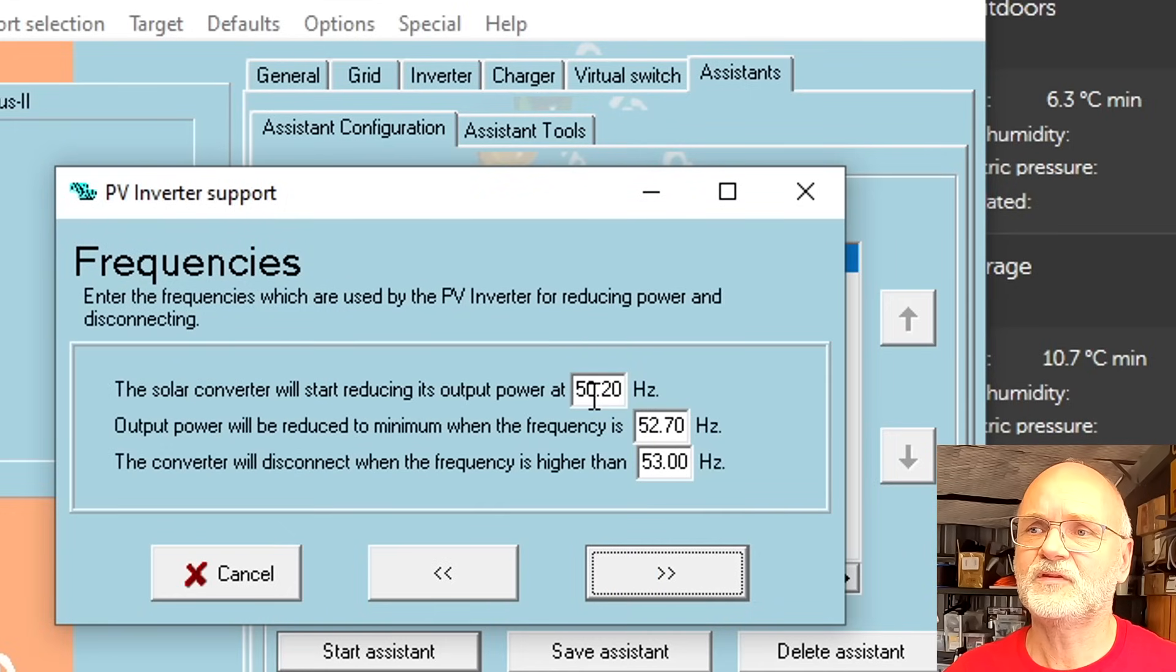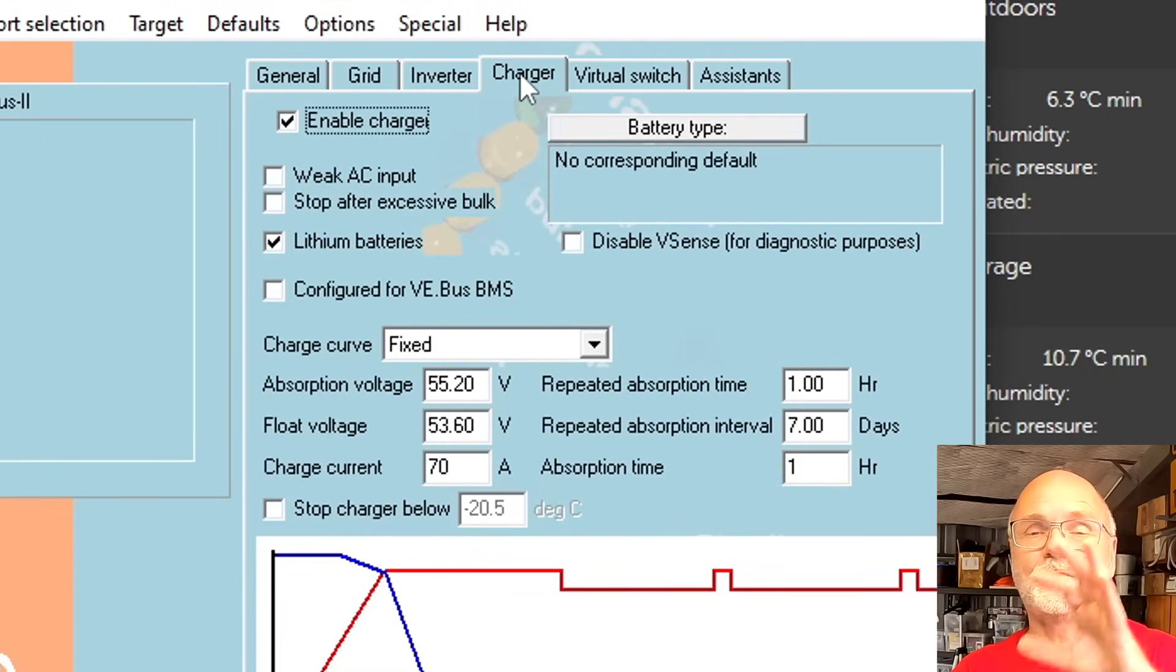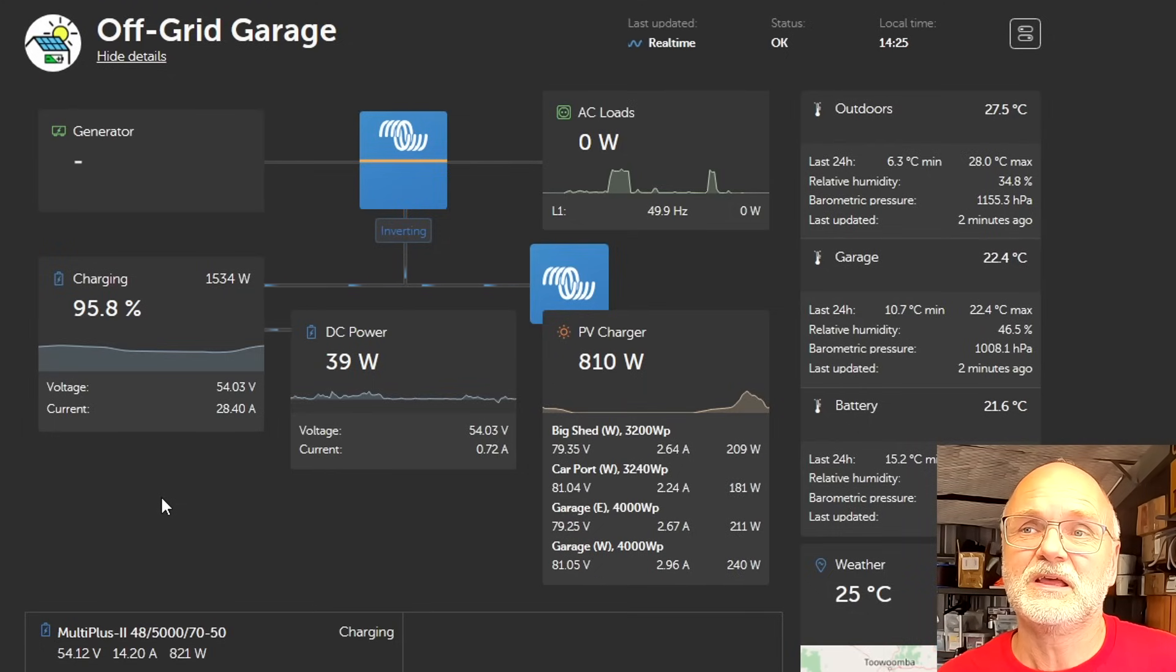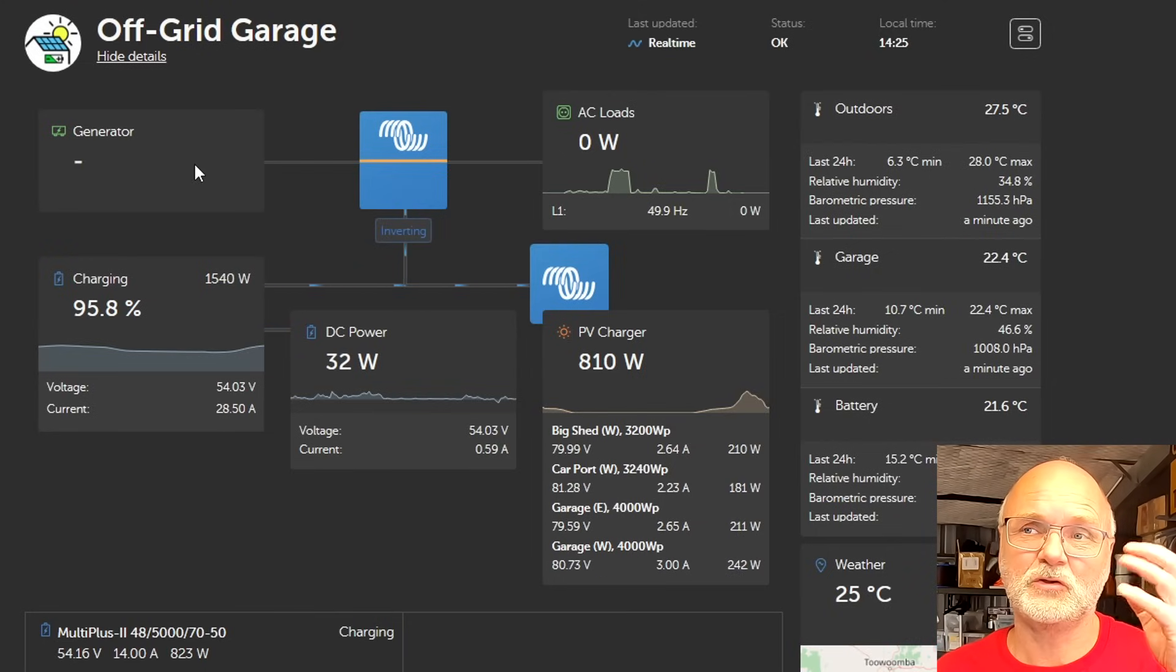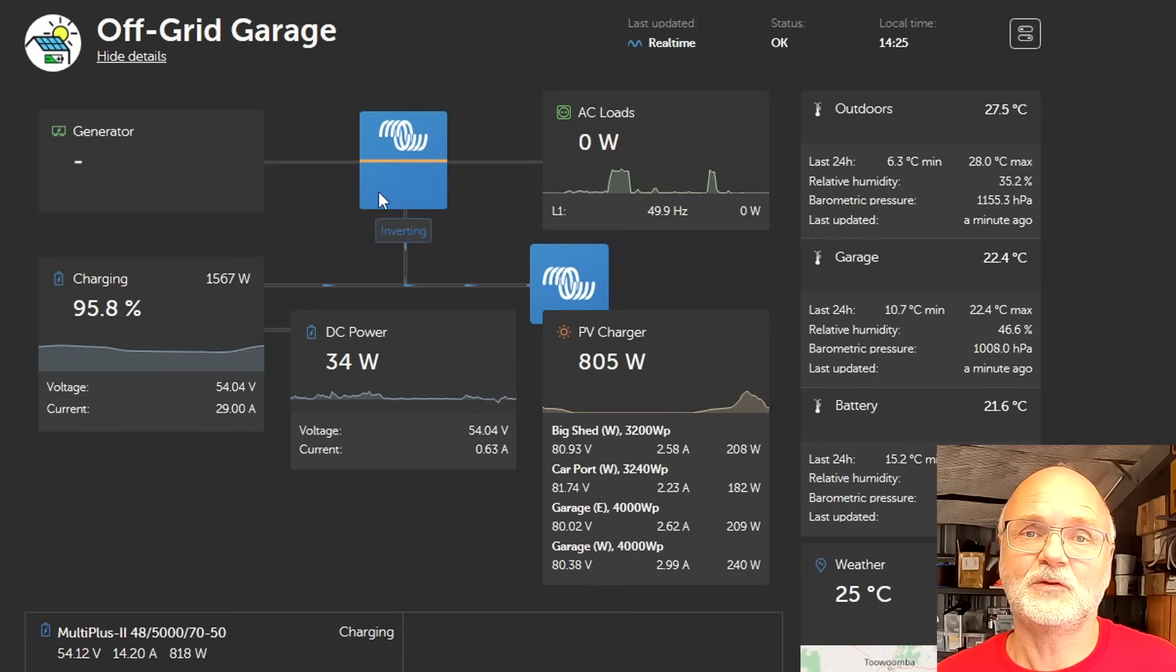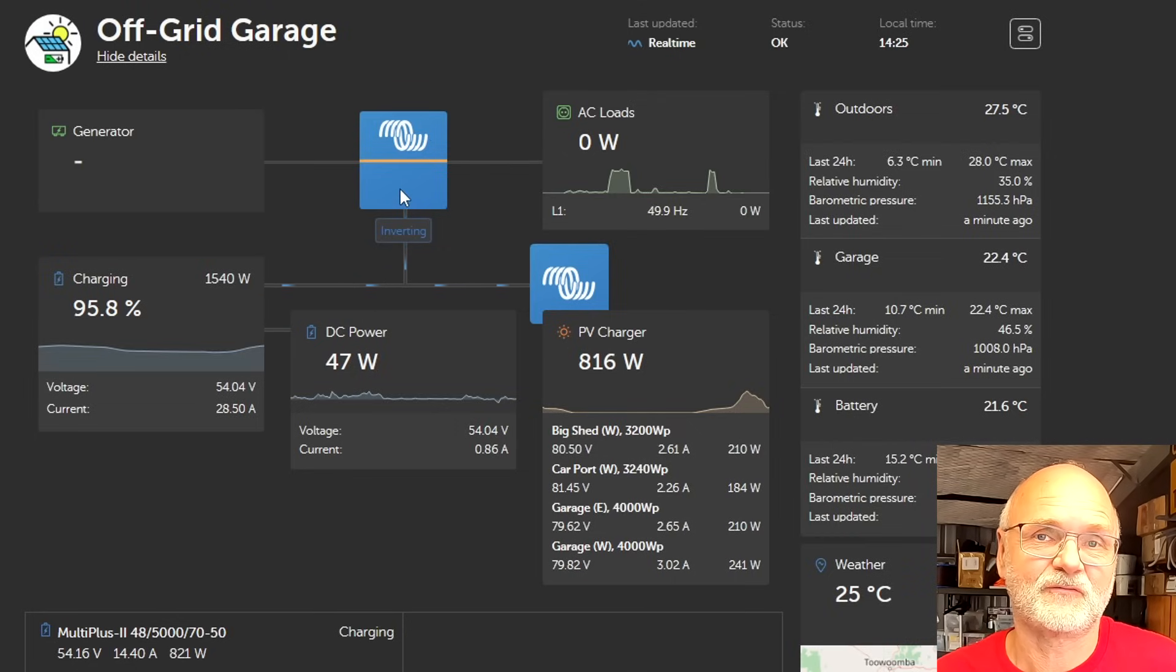The frequencies are 50.2 hertz when the micro inverter will start reducing power output and completely shut down at 52.7 hertz. I haven't changed any of these settings, this was all preset and actually fits the micro inverter. Then I tell the system my inverter is 2.2 kilowatts and I have 2040 watts connected on solar. This frequency shifting only works in off-grid installations and if you don't have a generator running or any other AC input into your multi plus. In an off-grid situation the multi plus is very flexible with the output frequency and can determine itself if it needs to increase the frequency or not.